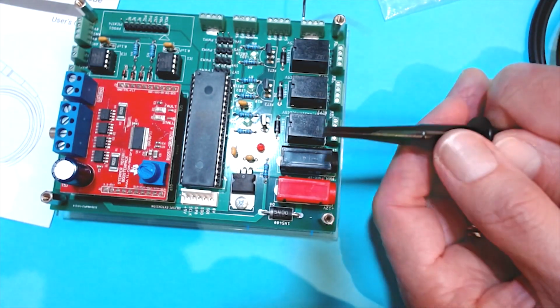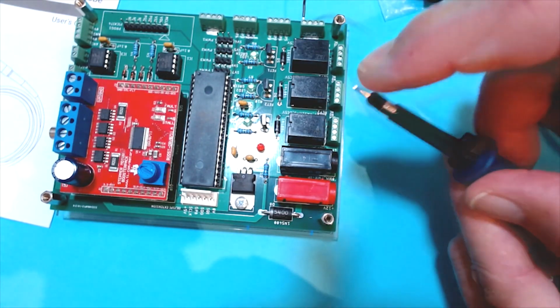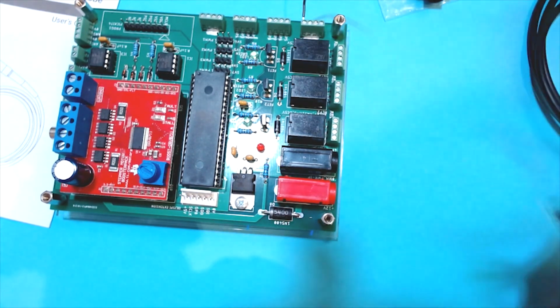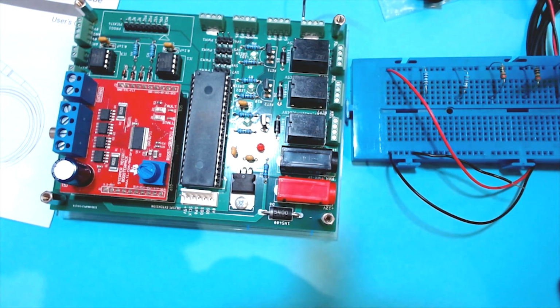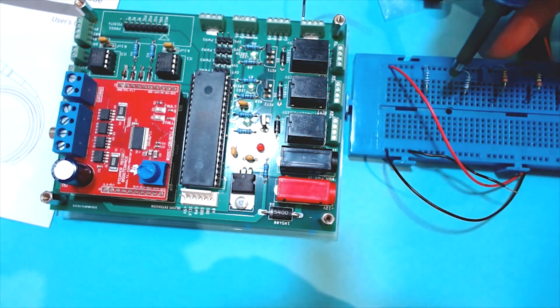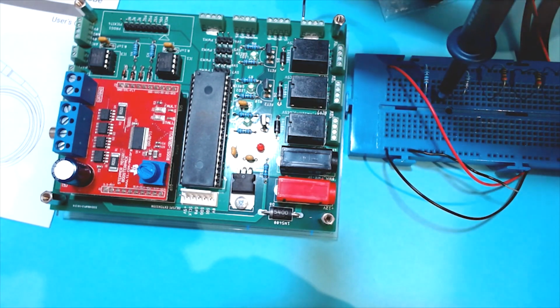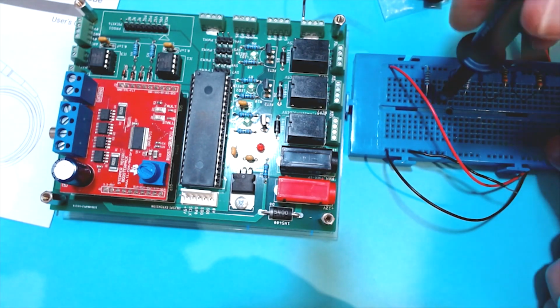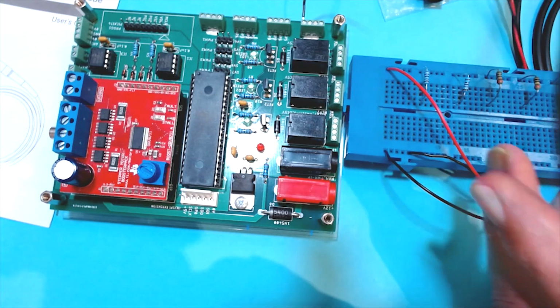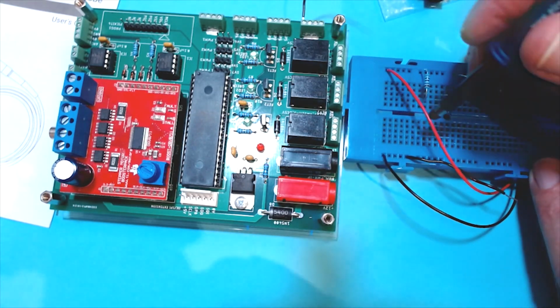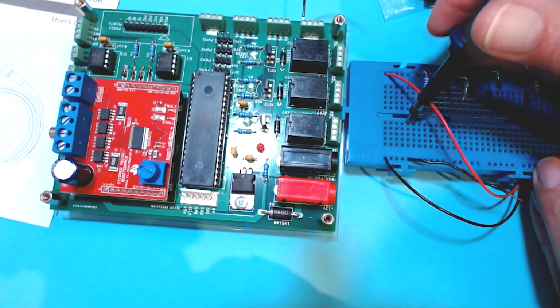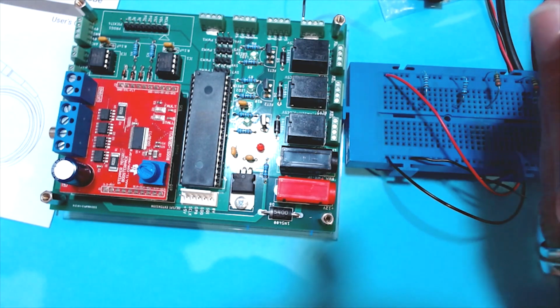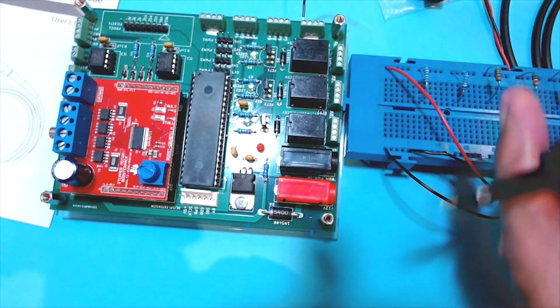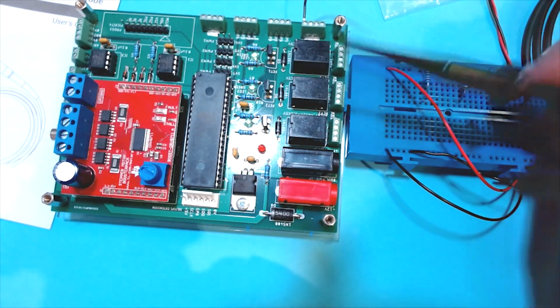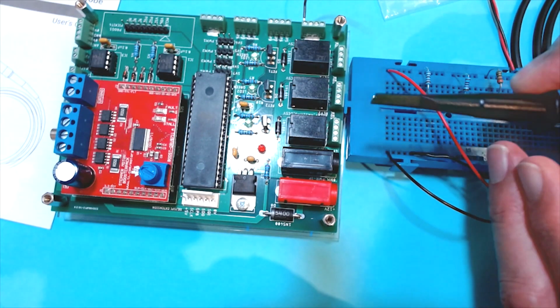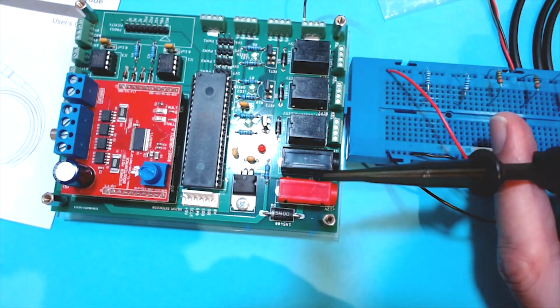The other thing I want to point out is that this tip here is very, very fragile. I know how tempting this will be - here's a piece of breadboard, and it's so tempting to stick this into one of these holes and leave it dangling in there. Believe me, you won't have a tip for very long. There's quite a lot of pressure on this cable, and when you put it into the board, you'll end up bending the tip over, and eventually it will snap, because they're not hugely strong. So it's best to protect this - I'd strongly recommend you make sure you've got your hook tip on your probe at all times, unless you're probing with one of the locating sleeves instead.